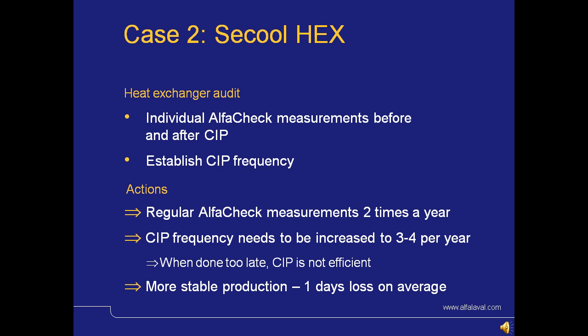Using this, we could establish a frequency for the CIP cleanings. How often do they actually need to be cleaned in order to keep the heat exchangers at optimal performance? The actions taken based on this are regular AlfaCheck measurements twice a year on each of the heat exchangers. Now, you can argue that once you do a couple of performance measurements on the heat exchangers, you would know how quickly it gets fouled up, and you can clean it when needed or in time.